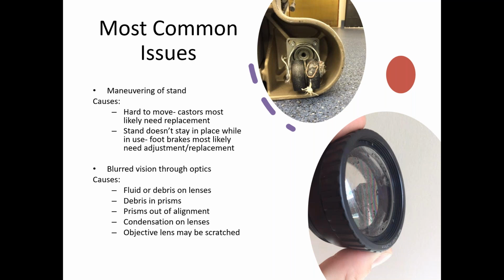And then on the way through to the objective lens, you can look for stains or grime or anything on the objective lens that needs to be cleaned off. A lot of times with the ophthalmology scopes, they'll use BSS solution, and it can sometimes spray up and contact that objective lens. On the newer objective lenses, they have what's called an apochromatic coating, and if that BSS solution stays on there long enough, it'll actually eat that coating away. What that will do is cause some focusing issues, and it causes them to lose the red reflex that they look for when they're doing cataract in the eye. So making sure that the objective lens is clean of stains and debris is good.